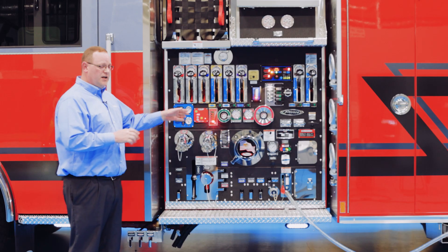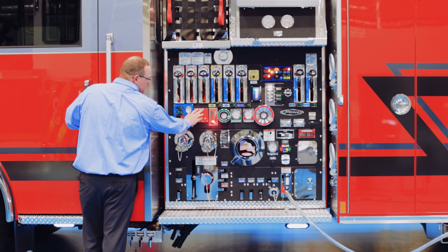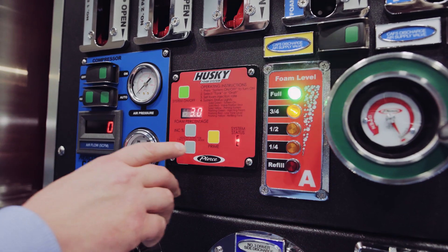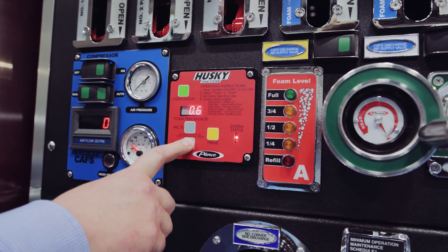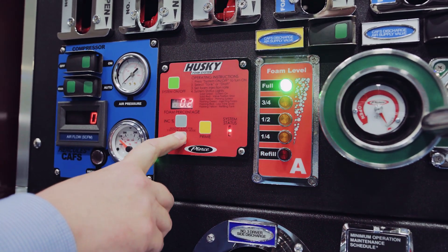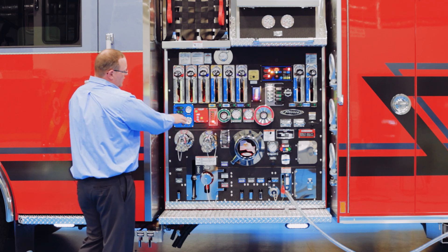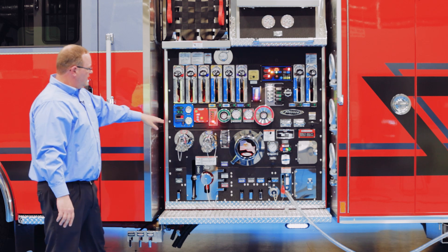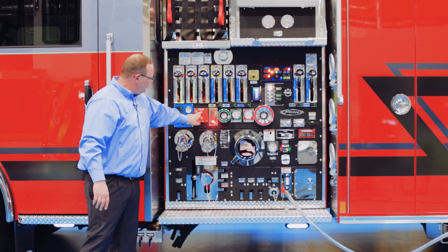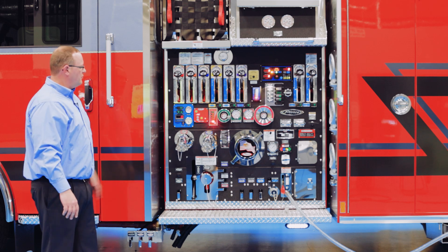Without further ado, let's get into the control head. One of the things you'll see with the Husky III foam system is that it has a very small footprint as far as the size of the control head. Your adjustments are some gray buttons here — you adjust foam percentages up and down. Your green button is your system on/off, your yellow button is your prime button, and you also have an LED status indicator system with a placard that shows you the system status when it's operating.